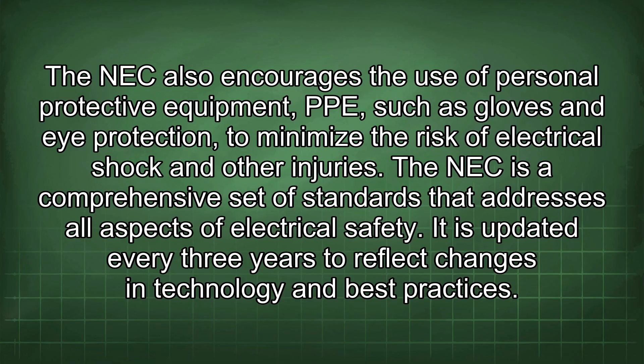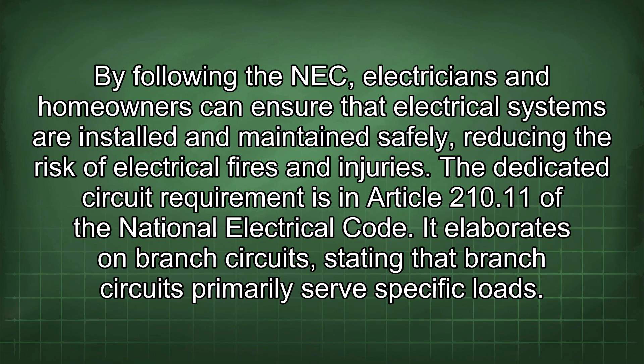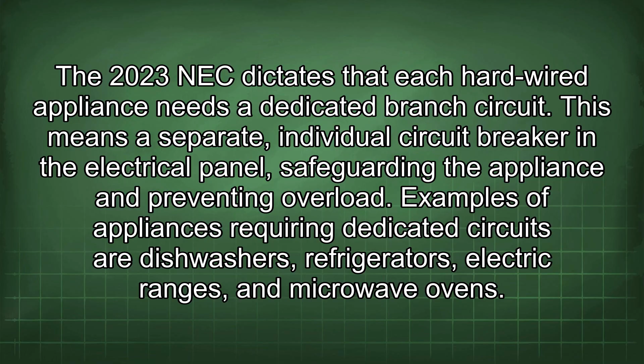The dedicated circuit requirement is in Article 210.11 of the National Electrical Code. It elaborates on branch circuits, stating that branch circuits primarily serve specific loads. The 2023 NEC dictates that each hardwired appliance needs a dedicated branch circuit. This means a separate, individual circuit breaker in the electrical panel, safeguarding the appliance and preventing overload. Examples of appliances requiring dedicated circuits are dishwashers, refrigerators, electric ranges, and microwave ovens. This addition minimizes the chances of overloading a circuit, especially when multiple appliances operate at once.